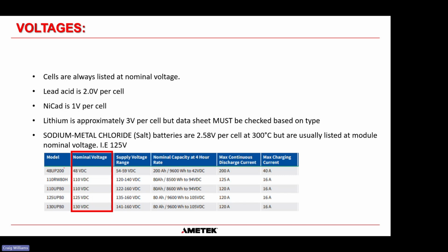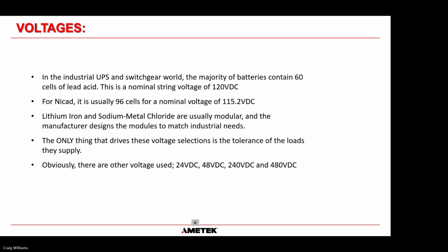So I put a table underneath here. This is the most popular one that we're seeing in the UPS and industrial facilities. It's a 125 UP80, and it's saying that the nominal voltage of that battery is 125 volts DC. So that is how the salt battery manufacturers are listing their nominal voltage. It's not by cell, it's by module voltage.